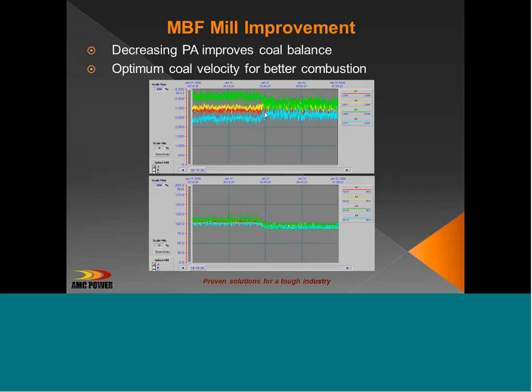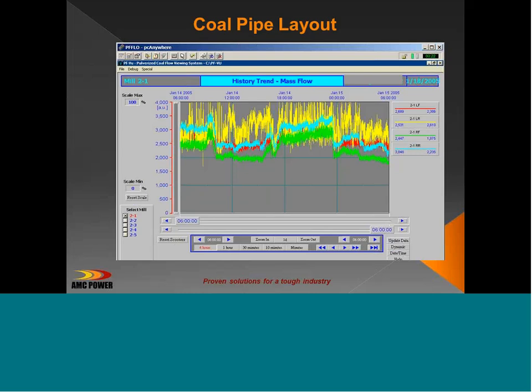What also happened at that time, with the new dynamic in the mill of a different PA to feeder curve, is the coal distribution changed. Now, this is not normal, but whenever you change something, it can have an effect on your coal distribution. And in this case, it improved our coal distribution without even needing to put in coal valves or anything like that. So through the use of primary air optimization and seeing how it affected the coal distribution and coal speed, we were able to solve a slagging problem on a Powder River Basin furnace.